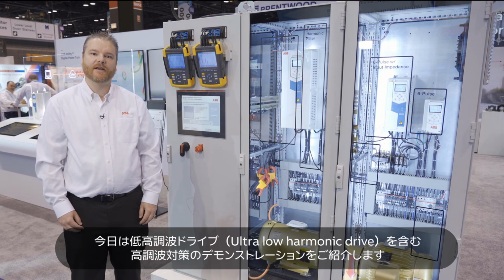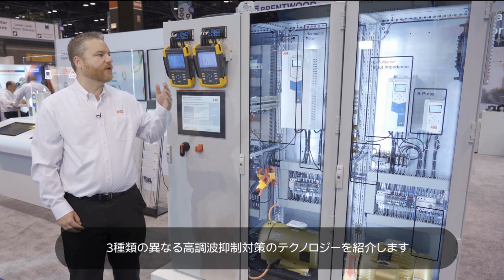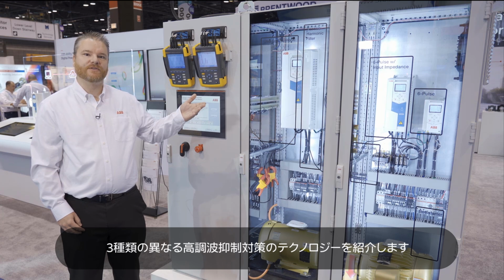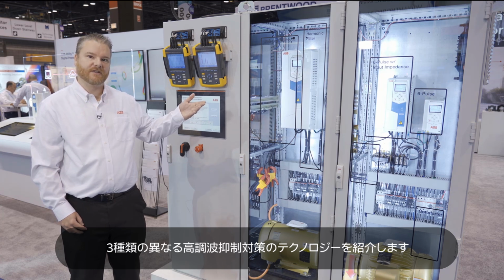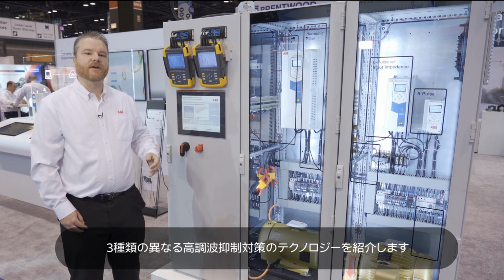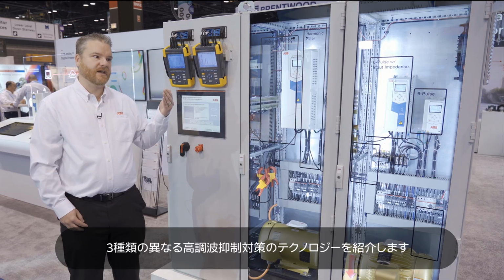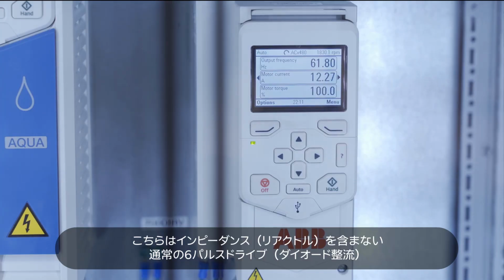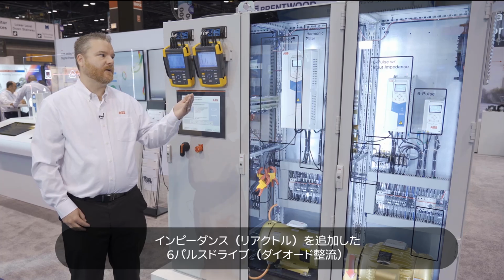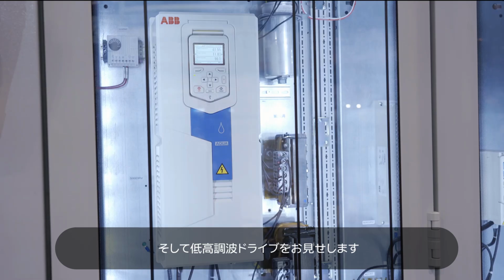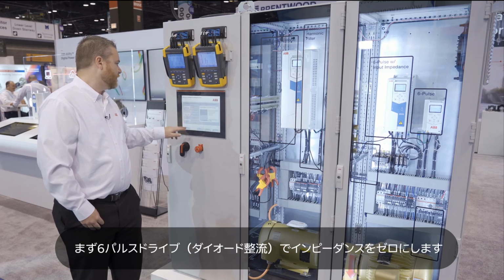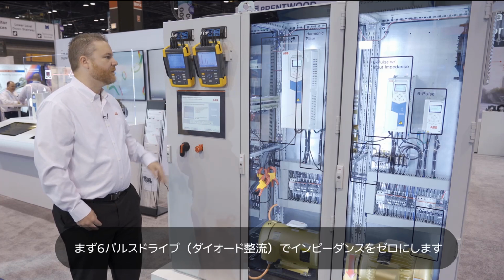including the ultra-low harmonic drive. So what we have here are 3 different technologies of drives, along with some additional harmonic mitigation technologies in this demonstration. What I'm going to do is start over on the far end and work our way towards me with a 6-pulse drive with no impedance, a 6-pulse drive with impedance built into it, and work our way all the way to an ultra-low harmonic drive. So I'm going to start with that 6-pulse drive with no impedance.